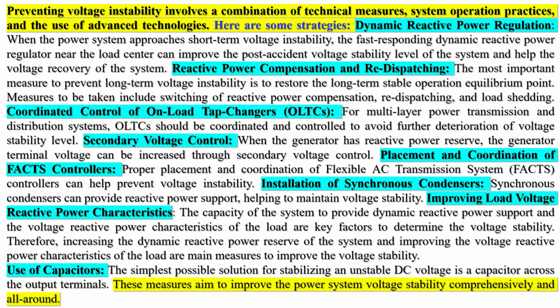For multi-layer power transmission and distribution systems, OLTCs should be coordinated and controlled to avoid further deterioration of voltage stability level. Secondary voltage control. When the generator has reactive power reserve, the generator terminal voltage can be increased through secondary voltage control. Placement and coordination of FACTS controllers. Another important aspect. Proper placement and coordination of flexible AC transmission system FACTS controllers can help prevent voltage instability. Synchronous condensers installation. Synchronous condensers can provide reactive power support, helping to maintain voltage stability.